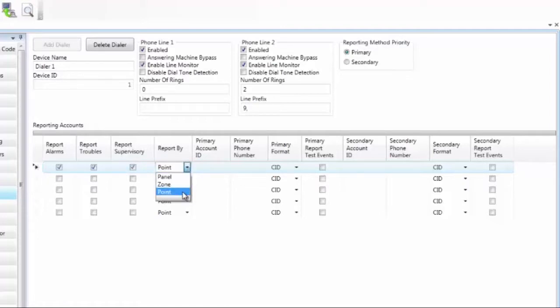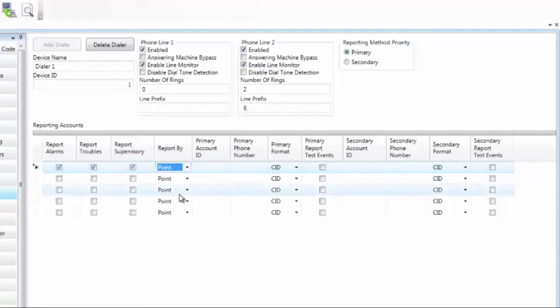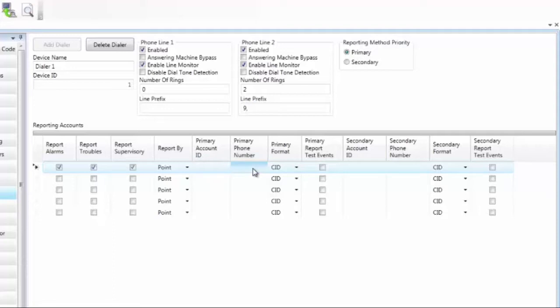Whether you want to send point information, which is going to give you all the specific information of the point that is in alarm. Zone information, which is going to give you the information of the zone that is in alarm. The zone number and the event in the zone. Or just the panel information. So the event on the panel is all that you will get. The default is point. Central station will give you an account number and you enter that here. The primary phone number. Central station will give you a phone number that you need to enter here, in which the UD1000 will dial when sending the information. So this is their phone number that they give you.